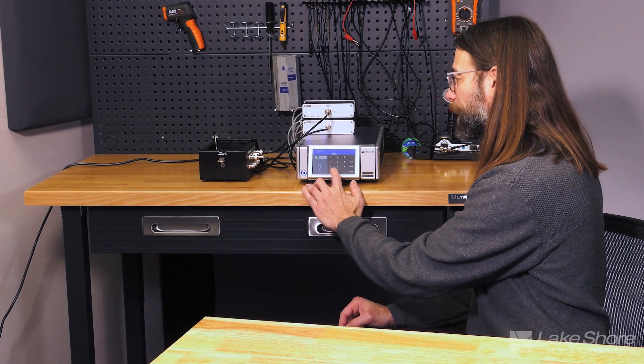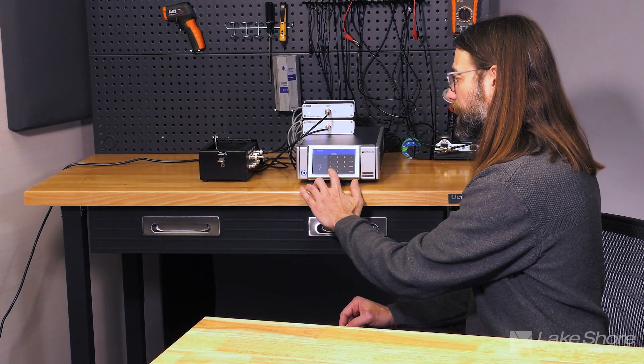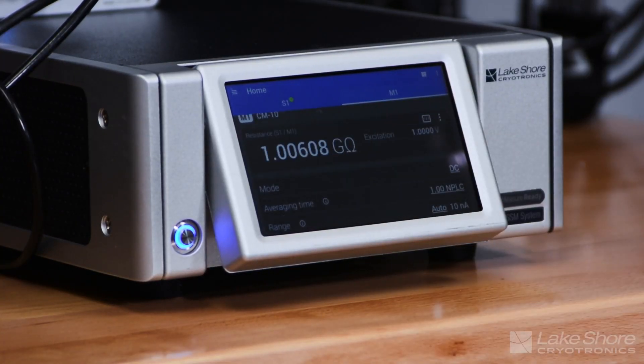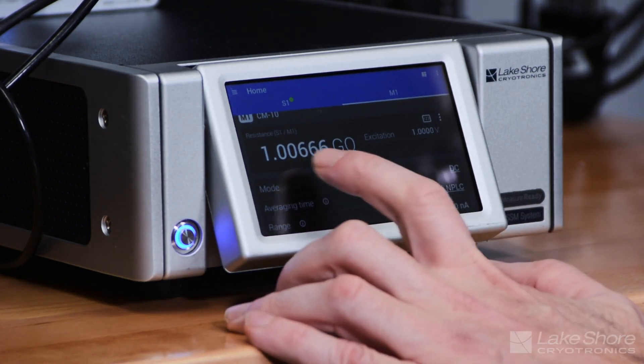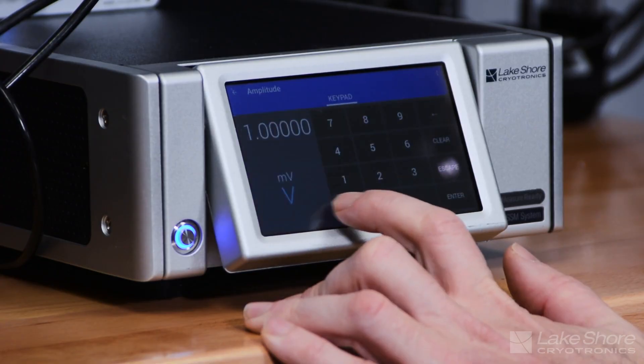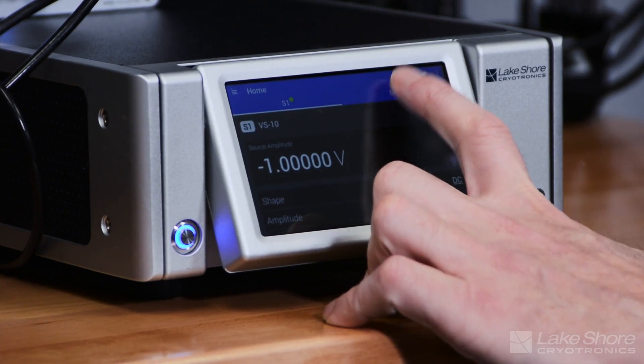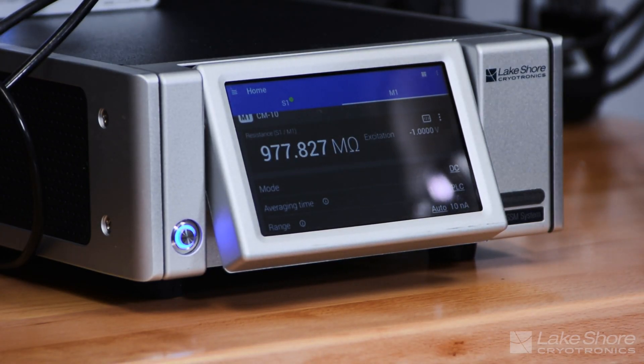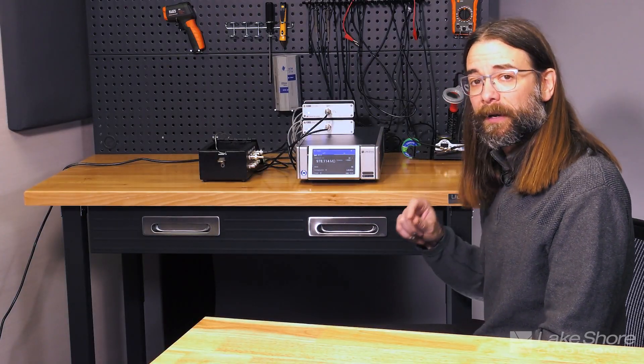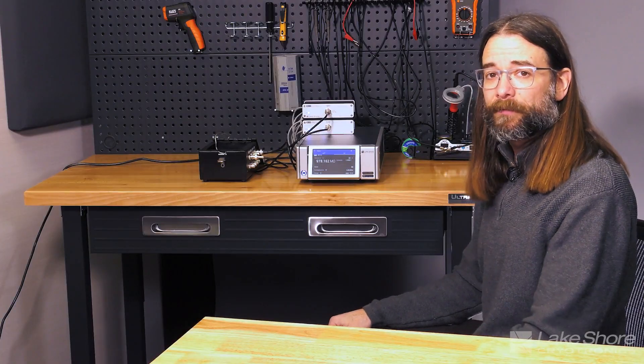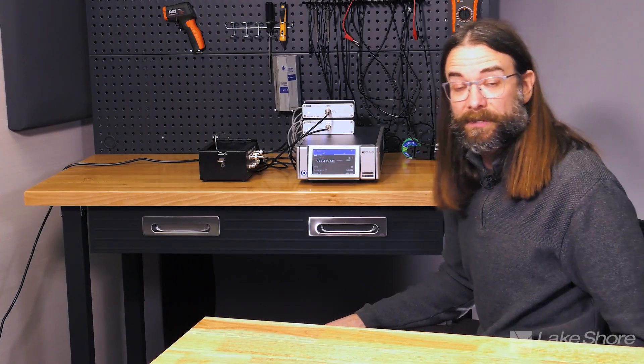So I'm going to go 1 volt DC and now go back over and take a measurement. Now you see I'm measuring 1 gigaohm but if I change that voltage to a minus 1 volt 978 megaohms. So you can see the discrepancy between plus and minus is going to get even greater as we decrease that voltage value. And again the primary reason for that is the offsets for the DC source and the measure.